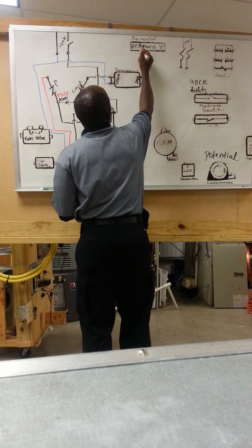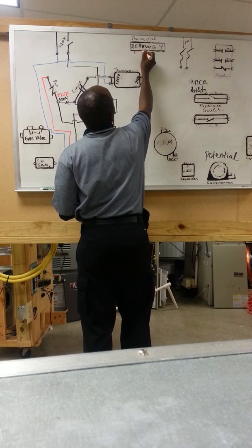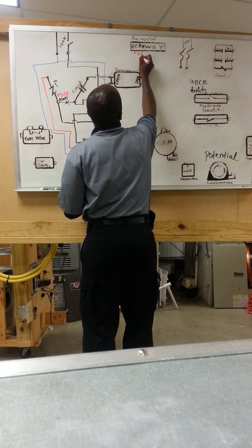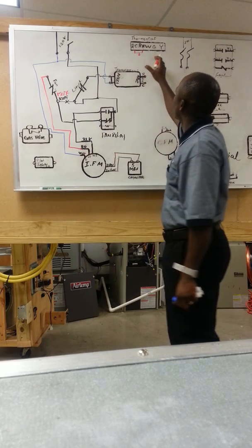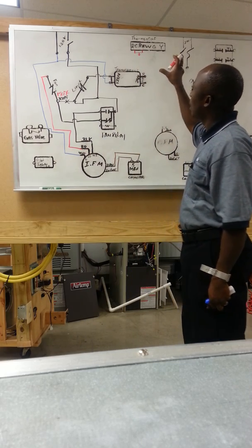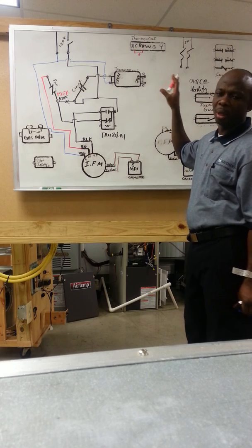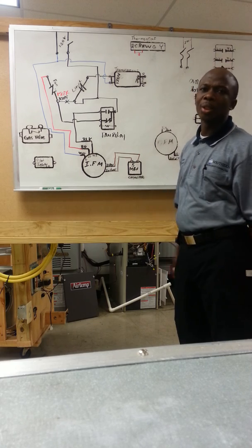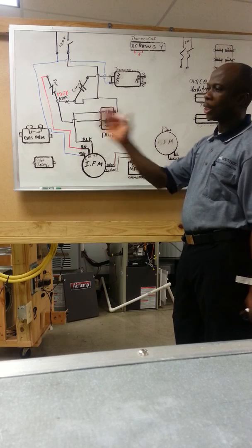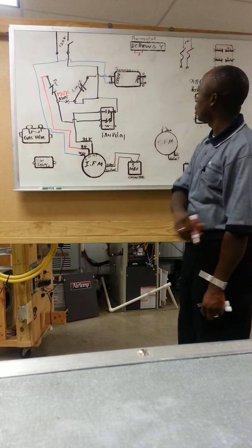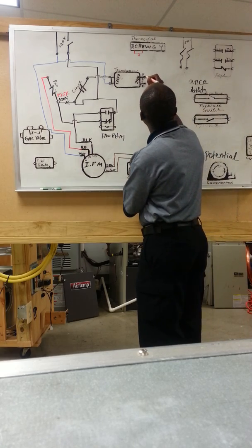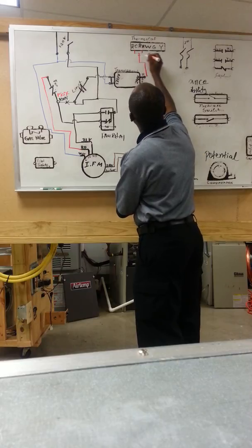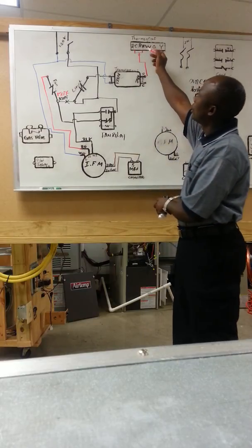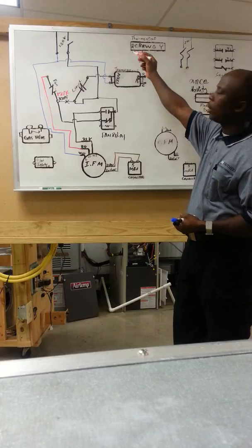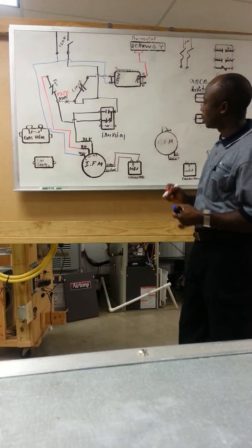So we're going to have to power this thermostat. It is called a 5-wire thermostat. 5-wire means the thermostat has 5 terminals. Anytime you have a 5-wire 24 volt thermostat, this thermostat is called an isolating thermostat. That means you can isolate the heating from the cooling or the cooling from the heating. So we're going to send power straight. I jumped the RH and RC, which is the 24 volt heating and cooling. I put them together, I send 24 volts to them.